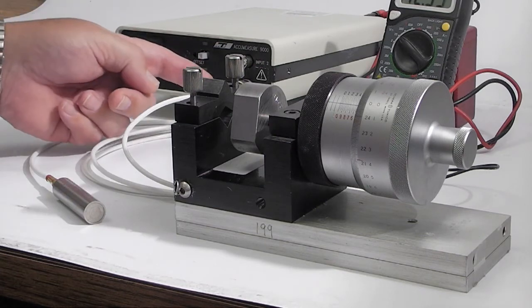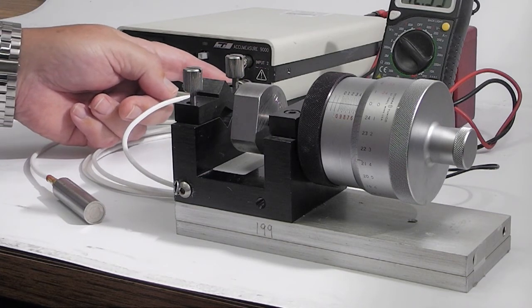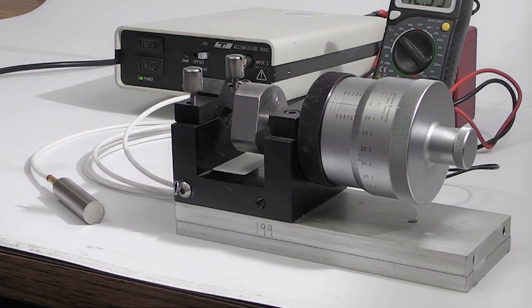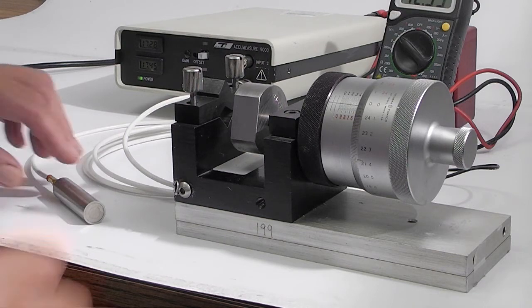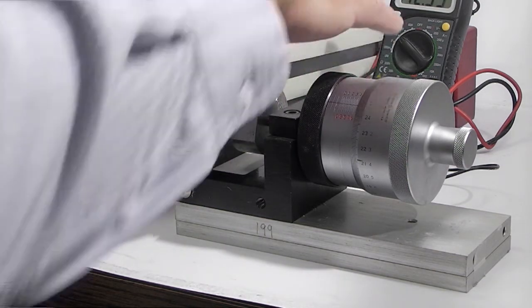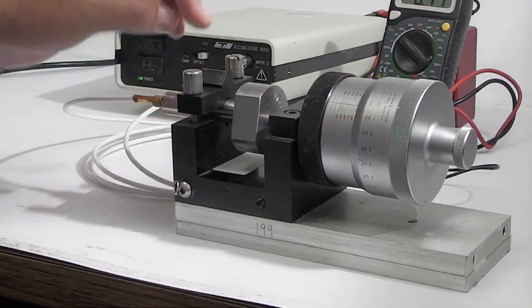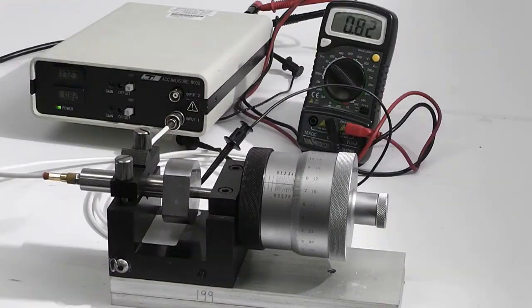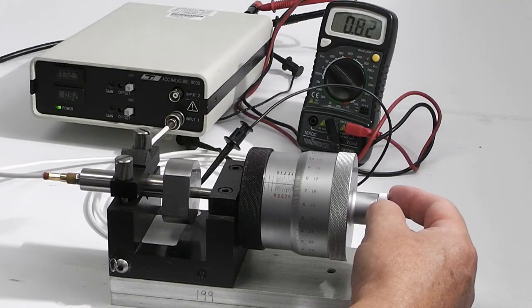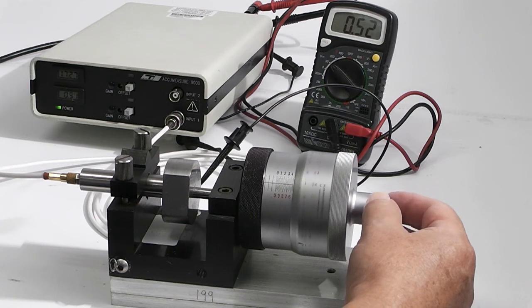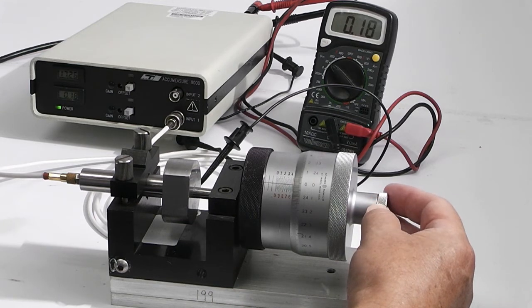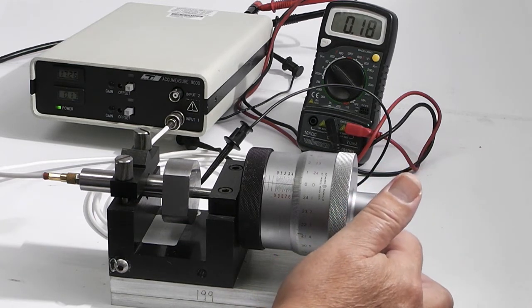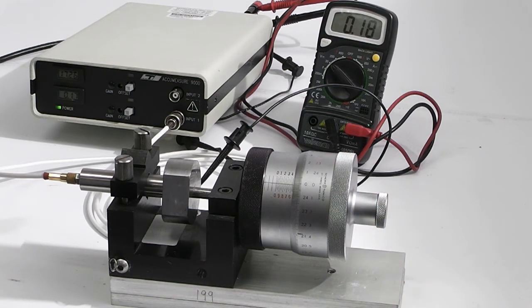The sensor probe's BNC cable is connected to the input or channel 1 front panel amplifier of the AS9000, and the sensor is mounted to the KDCH3 calibration fixture using the mounting clamp as shown. Insert it into the fixture and tighten the mounting screws and place the probe flush with the target. The micrometer on the calibration fixture is adjusted clockwise to contact the probe. And I've adjusted the reading so that it's at 0 on the micrometer.